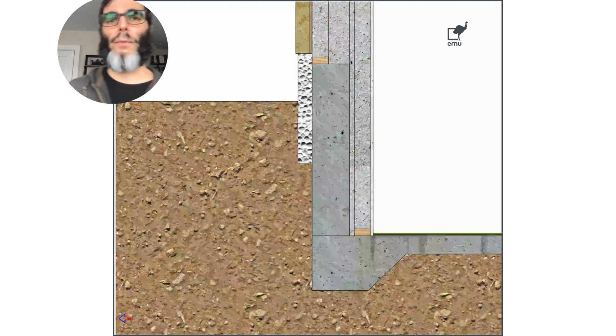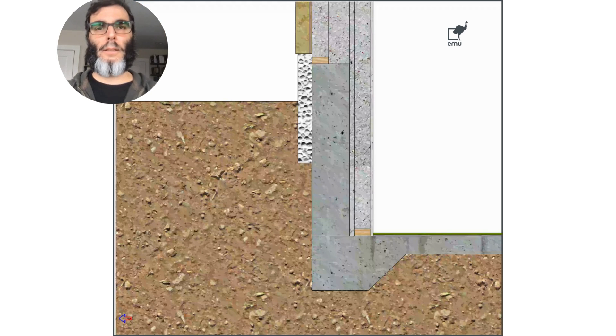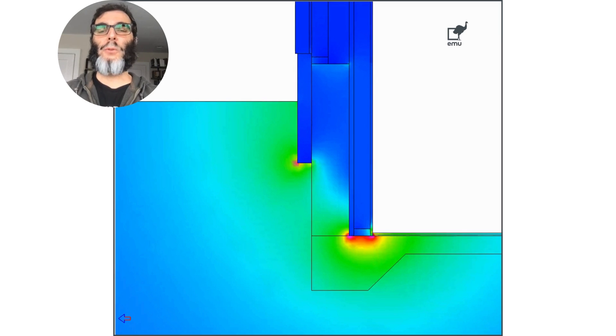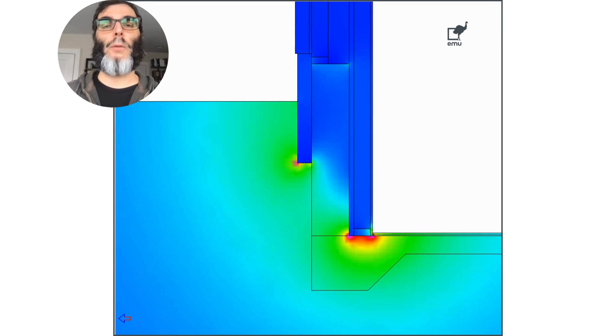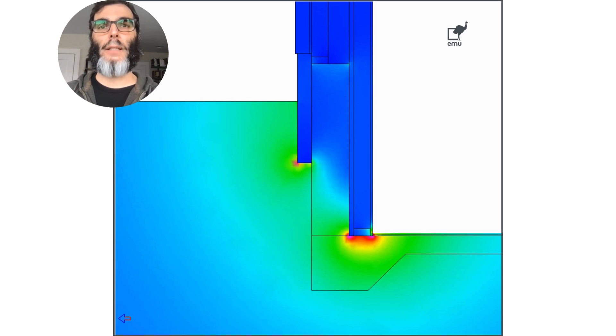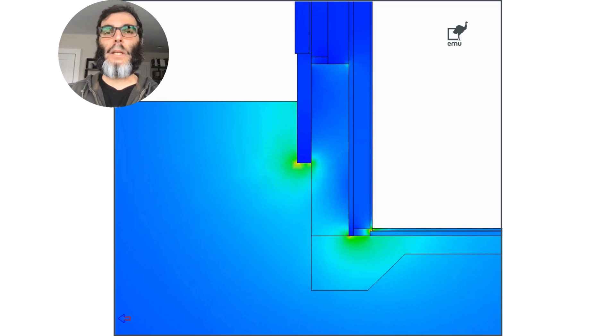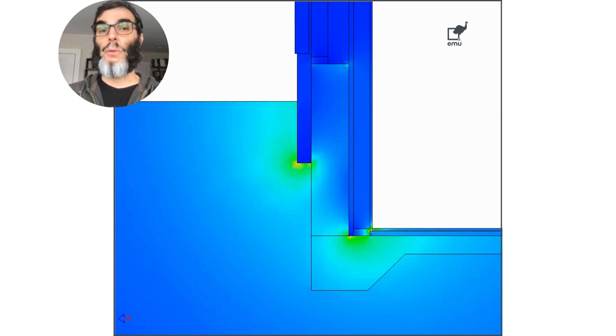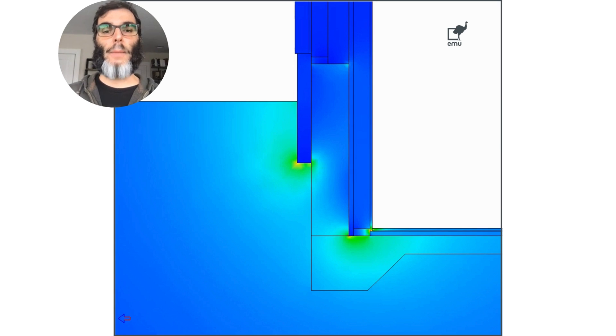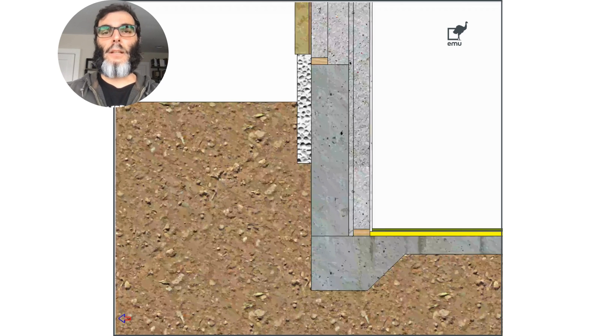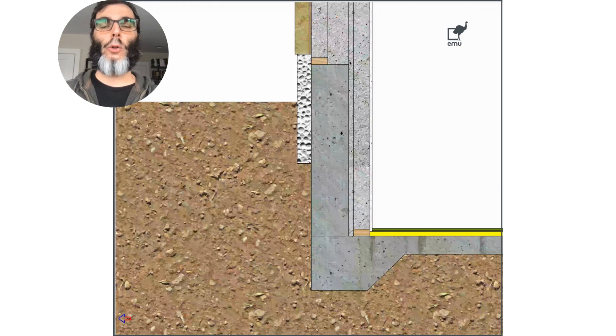Back to the original detail we got from the architects — this is what the detail looks like. Once we get to the heat flow intensity, this is what we get with the original detail from the architect. The heat flow intensity goes down significantly once we insulate the top of the slab, even just with one inch of poly-iso. You see that intensity goes down quite a bit. This is the detail close-up where we added the one inch insulation — it's the yellow line on top of the existing slab.